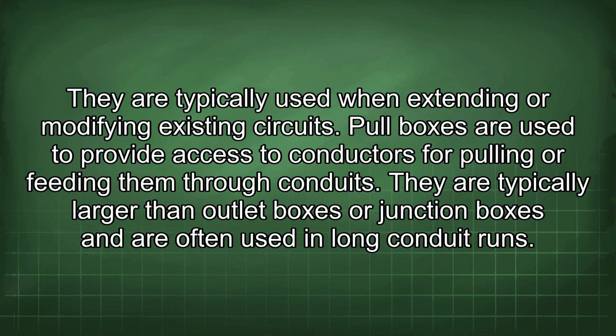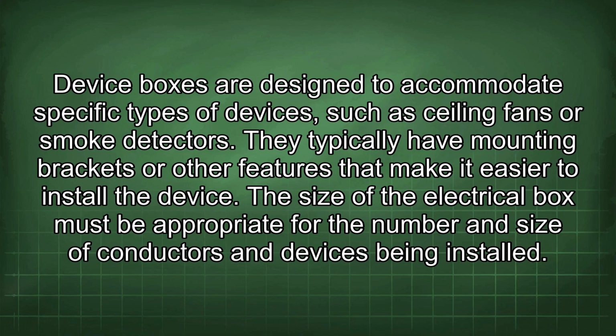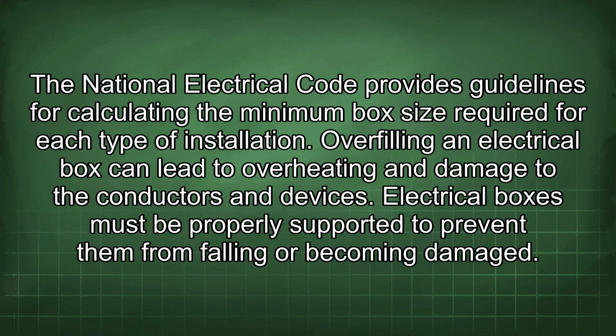Pull boxes are used to provide access to conductors for pulling or feeding them through conduits. They are typically larger than outlet boxes or junction boxes and are often used in long conduit runs. Device boxes are designed to accommodate specific types of devices, such as ceiling fans or smoke detectors. They typically have mounting brackets or other features that make it easier to install the device. The size of the electrical box must be appropriate for the number and size of conductors and devices being installed. The National Electrical Code provides guidelines for calculating the minimum box size required for each type of installation. Overfilling an electrical box can lead to overheating and damage to the conductors and devices.